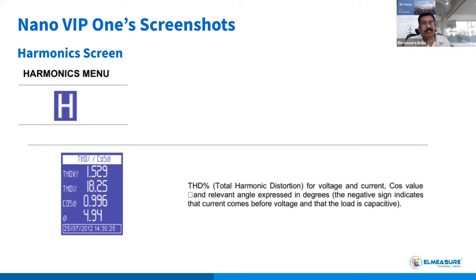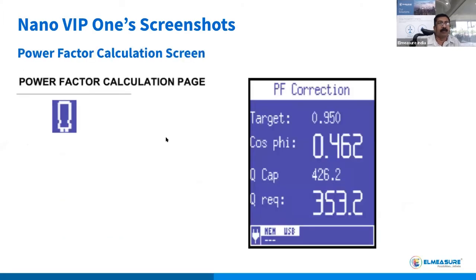So this gives the information as far as harmonics are concerned, the THD for both voltage and current, and it also shows the cos phi and the angle. The cosine angle will show some value here, and depending on the degree, whether the current is before the voltage, the load is capacitive. So either capacitive or inductive, it gives the parameter accordingly. This is the THD you get for whatever parameter we're talking about.